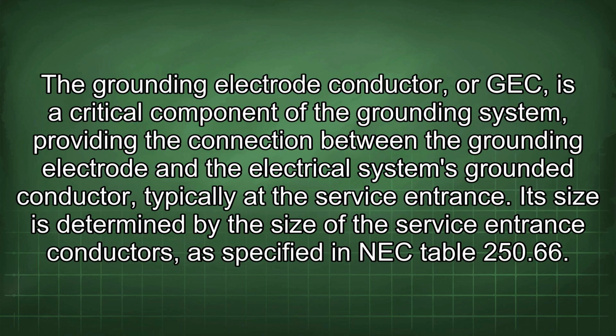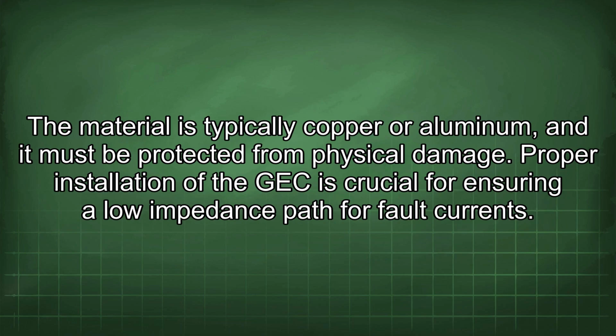The grounding electrode conductor, or GEC, is a critical component of the grounding system, providing the connection between the grounding electrode and the electrical system's grounded conductor, typically at the service entrance. Its size is determined by the size of the service entrance conductors, as specified in NEC Table 250.66. The material is typically copper or aluminum, and it must be protected from physical damage. Proper installation of the GEC is crucial for ensuring a low impedance path for fault current.